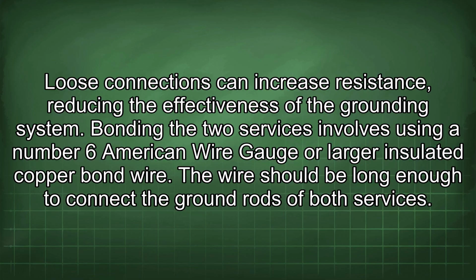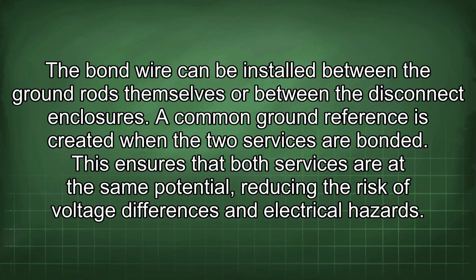Bonding the two services involves using a number 6 American wire gauge or larger insulated copper bond wire. The wire should be long enough to connect the ground rods of both services. The bond wire can be installed between the ground rods themselves or between the disconnect enclosures. A common ground reference is created when the two services are bonded. This ensures that both services are at the same potential, reducing the risk of voltage differences and electrical hazards.